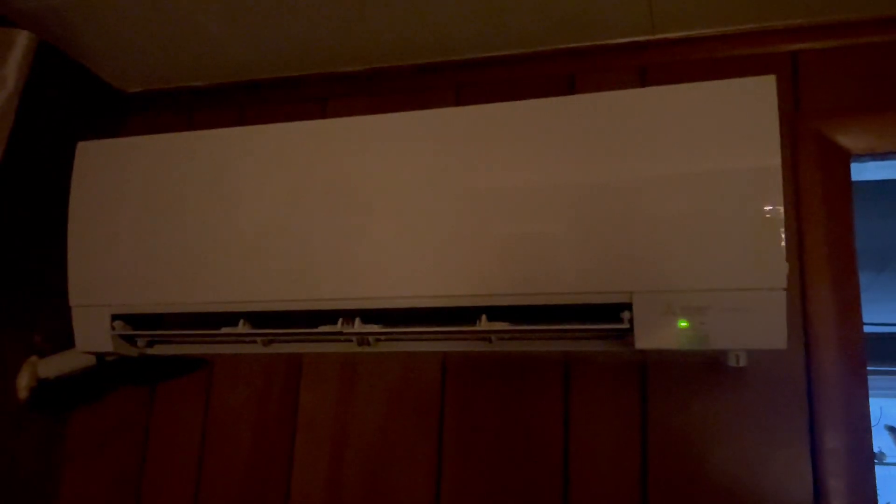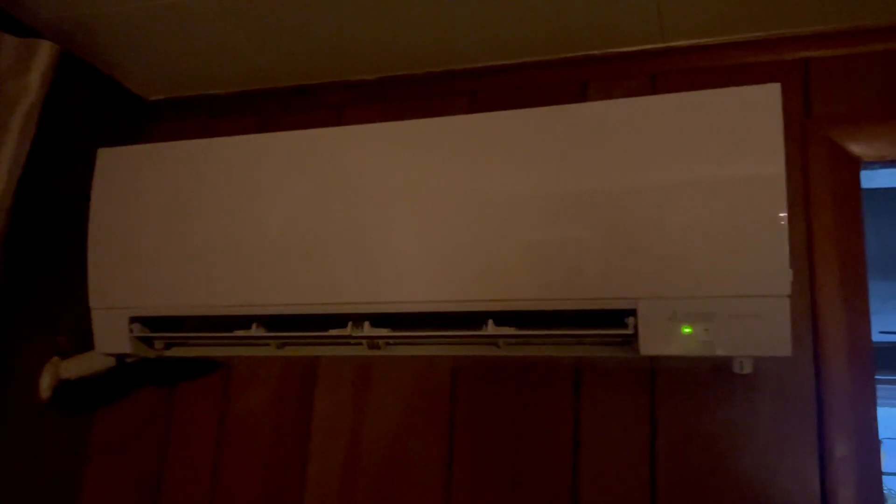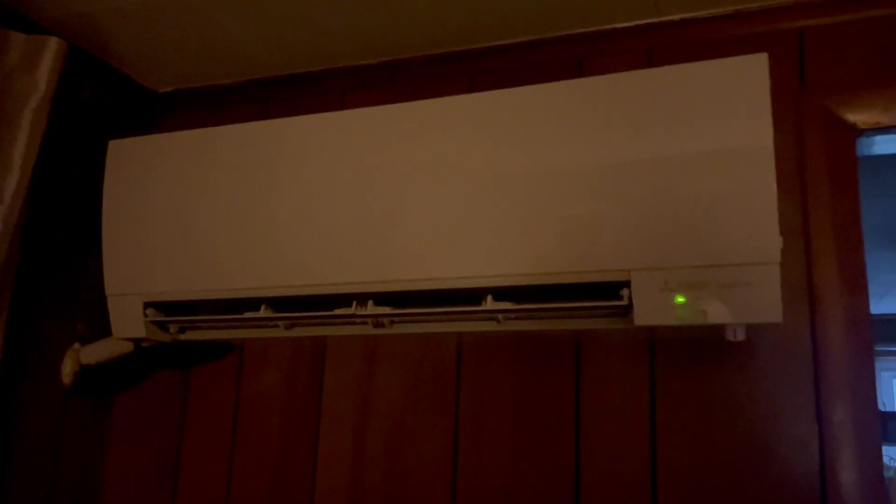It's an interesting way of doing it — really efficient as far as electric heating goes. But there's no way I would heat my whole house with this thing. We've been doing it for the last couple months, but real winter is coming. When you start getting down to single digits or below zero, this thing just won't cut it. It barely keeps up when it's in the upper 20s — fan on maximum high and it has a hard time maintaining the temperature. Anyway, that's the mini split.